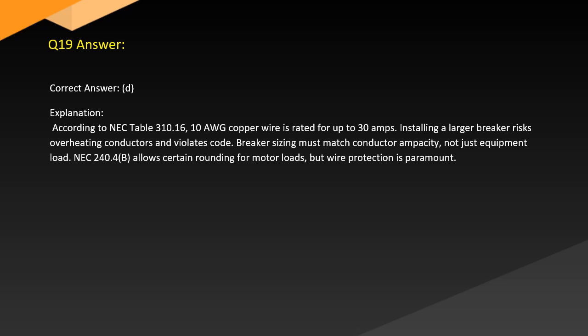According to NEC Table 310.16, 10-gauge copper wire is rated for up to 30 amps. Installing a larger breaker risks overheating conductors and violates code. Breaker sizing must match conductor ampacity, not just equipment load. NEC 240.4(B) allows certain rounding for motor loads, but wire protection is paramount.